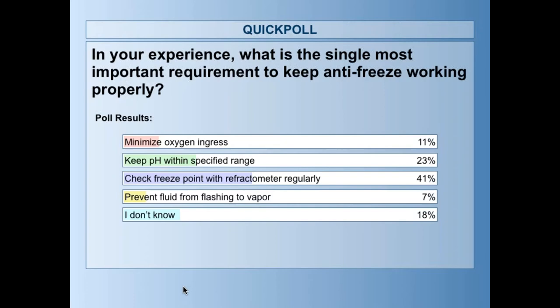The best way is to check with the refractometer, as most people have indicated here. Then a quick check is your pH within your specified range. Now, that's only a quick check. Your pH could be within your specified range, but if your glycol was mixed with water that had minerals in it, it might not change the pH, but as we learned from Jeff Persons, those minerals will react with the glycol inhibitors and come out of solution. So your freeze protection drops even though your pH looks good.